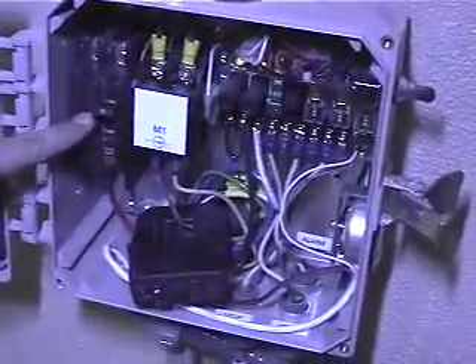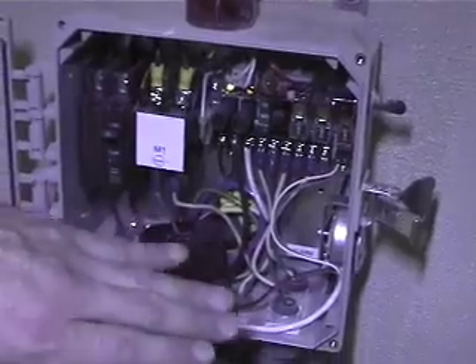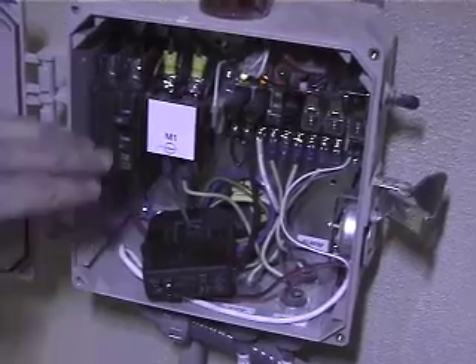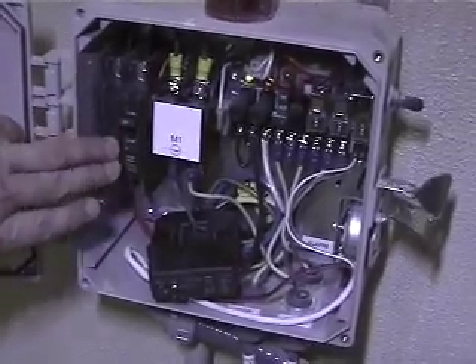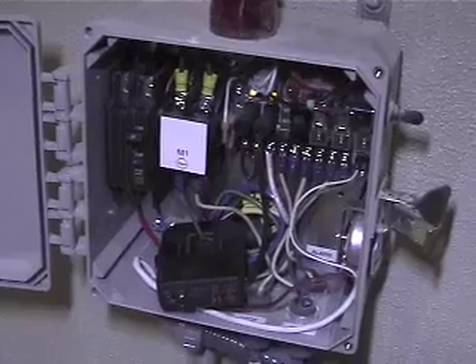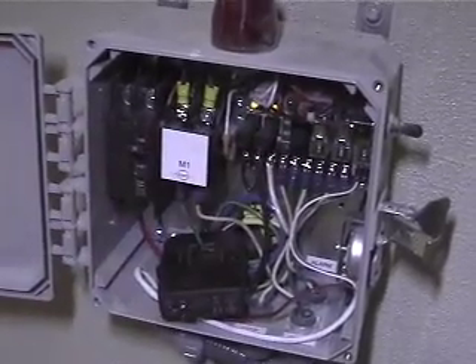If you did need to shut power to the pump or to the control system, there's 2 switches in here. We've got this circuit breaker, which will kill power to the pump, and we've got this switch that we can just turn to off, which would be right in the middle position, and that would shut off power to the contactor, which would pull in order to energize that pump. But if this was off, the pump wouldn't energize anyway, because this is the circuit breaker for the power for the pump. So that needs to be on auto. It pretty much is self-contained.